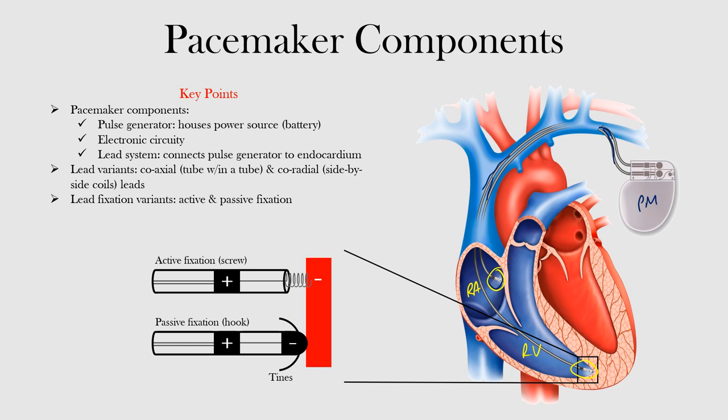The pacemaker battery is used to deliver pacing pulses, sensing — meaning it can analyze the electrical activity of the heart — and they can store cardiac biosignals. The pacemaker is often powered by a lithium battery that has a lifespan of about five to ten years. If the pacing requirement or stimulus threshold is high for a patient, this may shorten the battery lifespan. Once the battery is depleted, the entire system needs to be replaced.